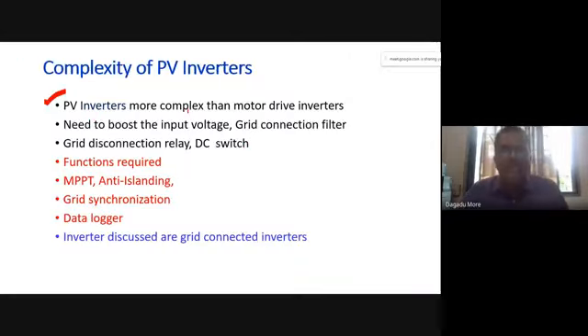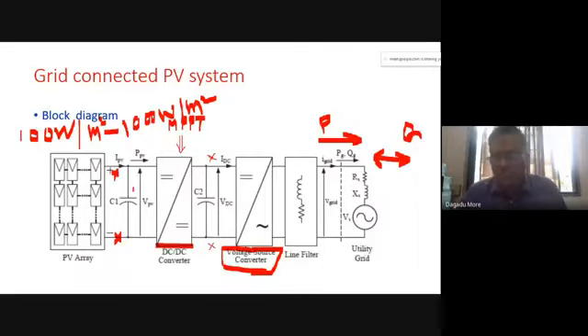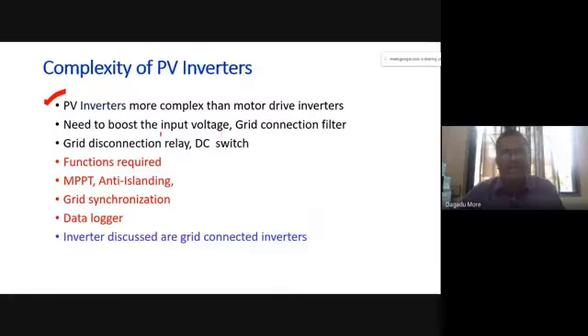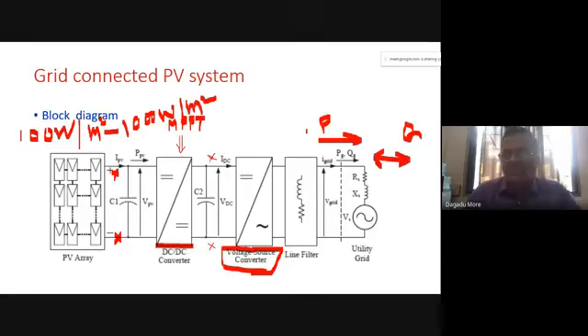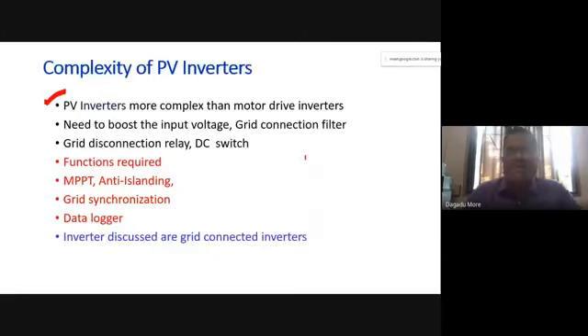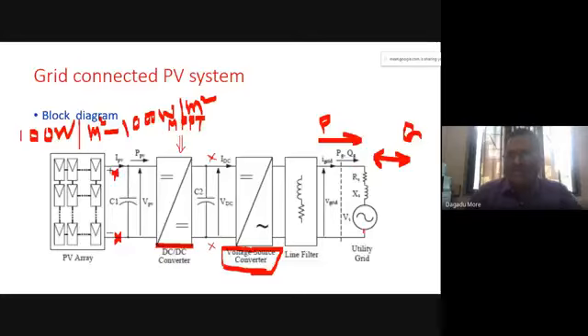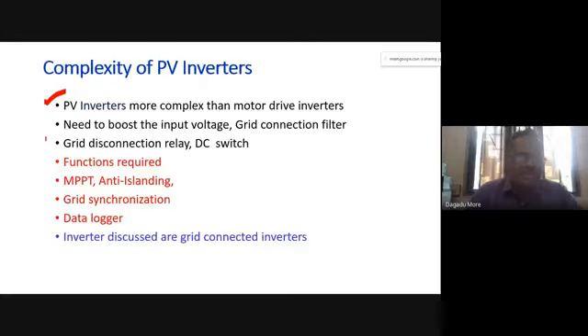We have seen that we need to boost the voltage. So we require a DC to DC boost converter. Then we require a grid connection filter, a filter at the line side or grid side. Then when the grid has failed, when the grid supply is off, we require a grid disconnection relay. Let us assume it is placed in between. So when the supply fails, our PV system should be disconnected from the grid. That is the grid disconnection relay.